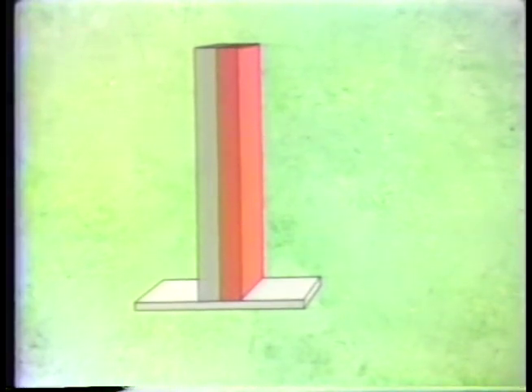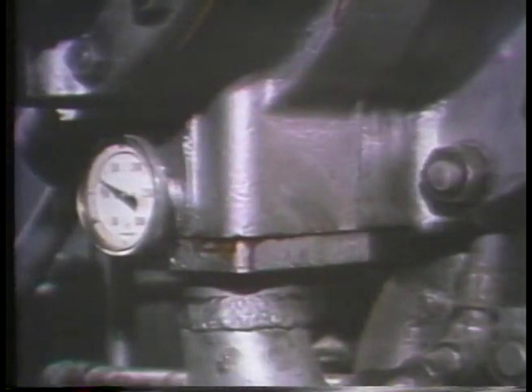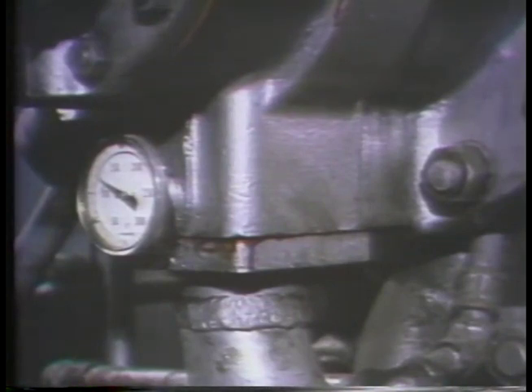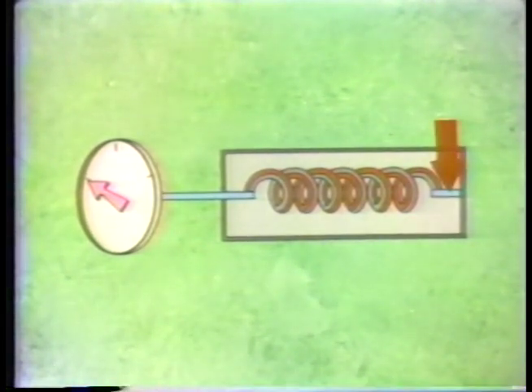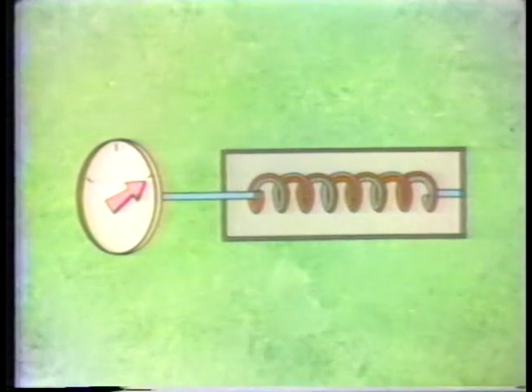When the temperature around the sensing element changes, the two metals expand or contract at different rates, causing the element to move. This movement is in direct proportion to the temperature change. Most bimetallic thermometers used in the plant are more complicated — for example, this one contains a bimetallic element which is helically wound. The helical shape produces a long, slender sensing element which allows for good penetration into a thermowell or directly into whatever is being measured. One end is fixed in position while the other end is connected to a rod and pointer. Changes in temperature cause the element to coil or uncoil, resulting in rotation of the rod, and the pointer indicates the temperature.